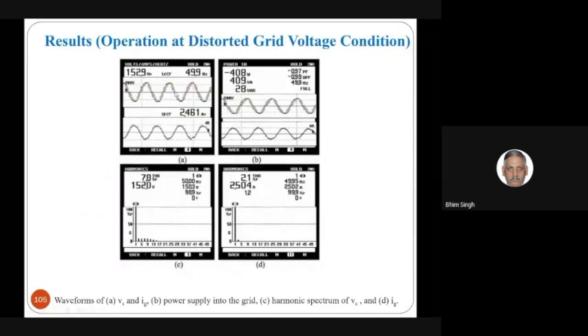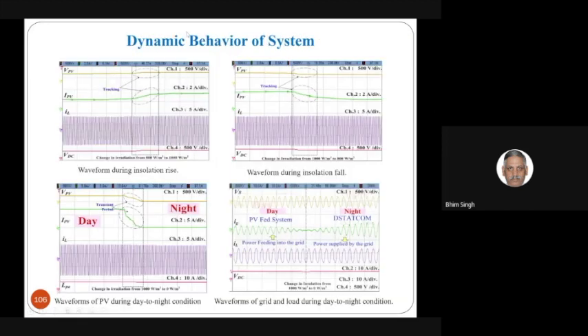And then under distorted voltage, the control is also modified. The voltage THD is 7.6%, but the current THD is still 2.1%. So we have to use another set of filters on the grid voltage before using it in the control, so the control is modified for that. And these are the dynamic behavior of the system when the solar panel power is increasing, and accordingly, of course, the load is not affected, and likewise as the solar panel power is reducing. In the daytime you have solar generation, but in the night you don't. But still, it does not get disturbed.